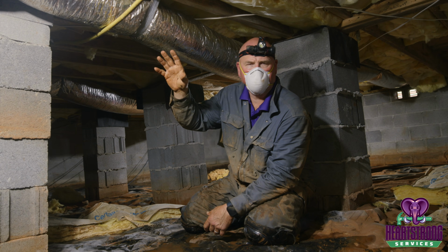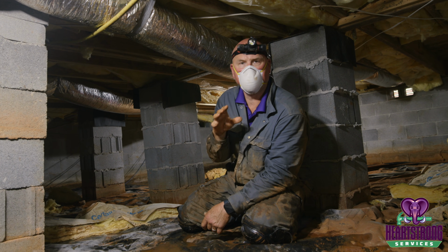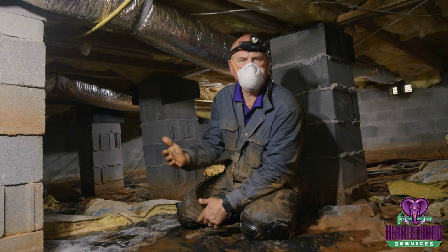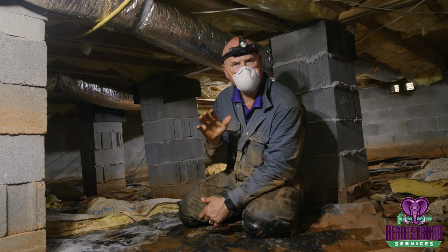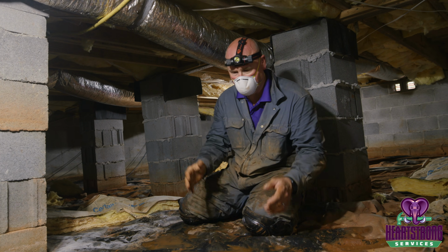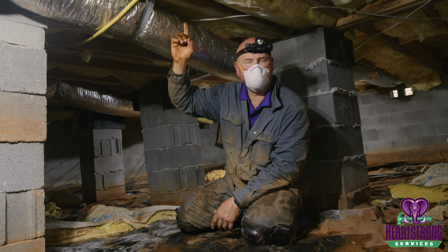There's an important step that'll happen with our company before we can even begin the work, which is we're going to actually come out to the home before we start the project. In other words, when a customer signs up with us, typically in about 24 to 48 hours, we send a technician out to do a temporary dry out. What that means is this environment is way too wet, with the standing water, the sweating ductwork, and the moisture content on the wood.